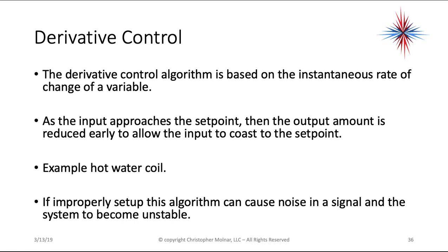Derivative control algorithms are based on the instantaneous rate of change of a variable. As the input approaches a set point, the output amount is reduced early to allow the input to coast to the set point — for example, reducing the valve position of a hot water coil as space temperature nears set point to avoid overshoot. However, if improperly set up, this algorithm can cause noise in a signal and make the system unstable, where it fails to maintain temperature at all.